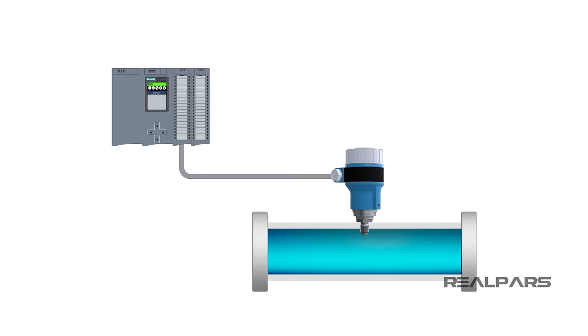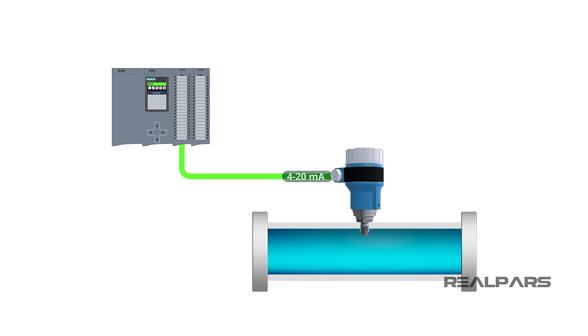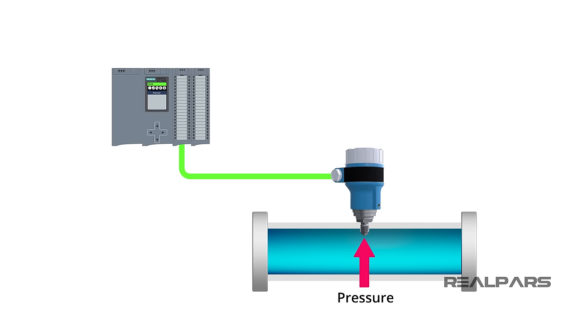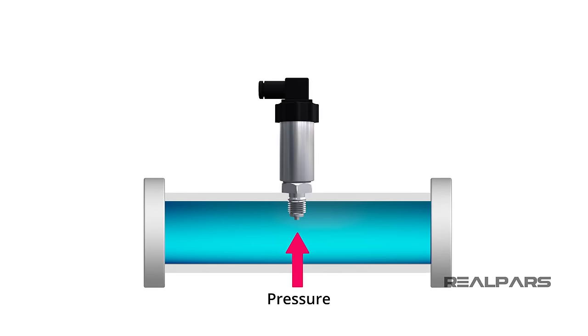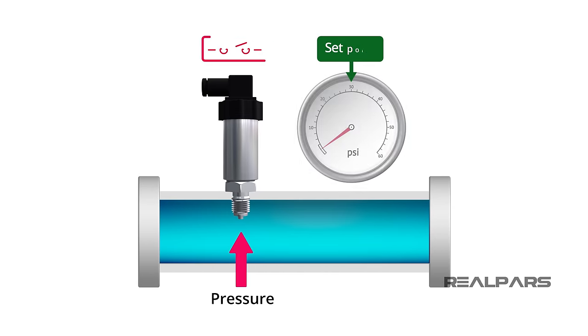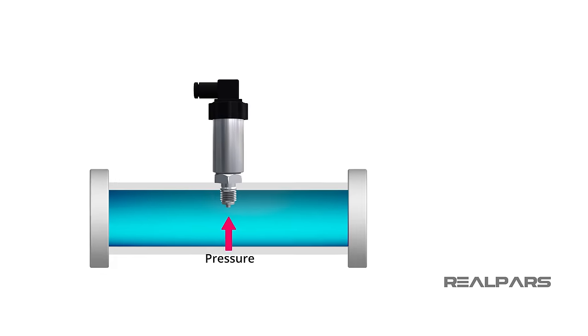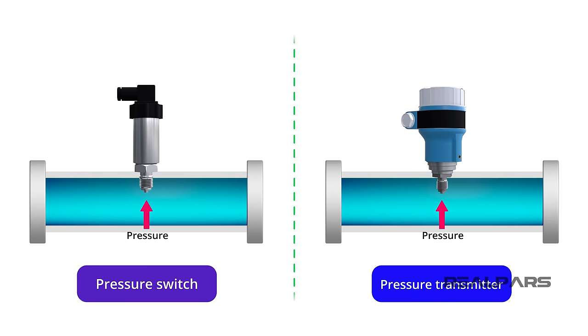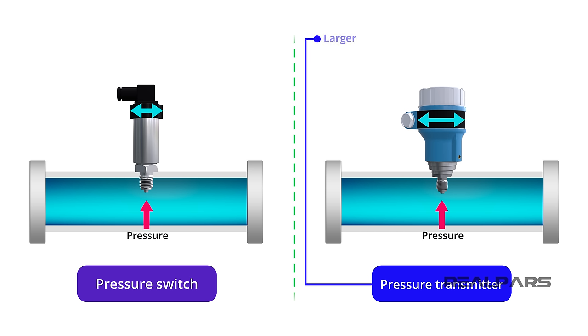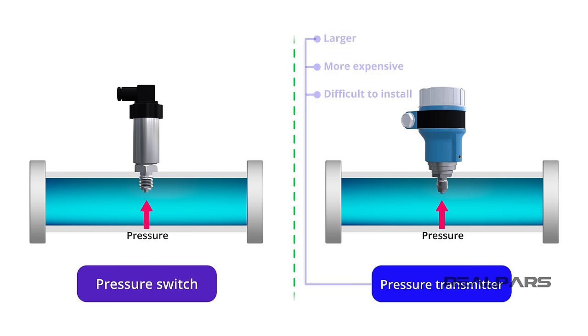As we've already discussed, a Pressure Transmitter produces an analog electrical voltage or a current signal representing 0 to 100% of physical process pressure. A Pressure Switch has electrical contacts that open and close at a specific pressure. Can a Pressure Transmitter be used to function as a Pressure Switch? The answer is absolutely yes, but is it really worth it? First of all, a Pressure Transmitter is larger, more expensive, and often more difficult to install. There are other deterrents as well.